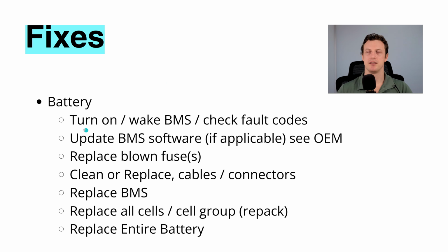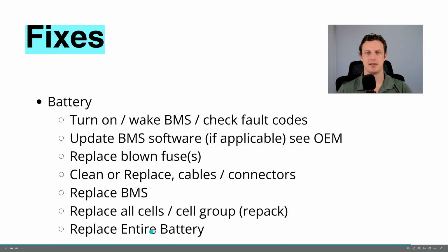For the battery, you can start by turning on or waking the BMS, or checking it for fault codes if it has that capability. You might also be able to update the BMS software if applicable - see the OEM of that BMS. Replace any blown fuses, clean or replace cables, wires and connectors, replace the BMS itself, replace all cells or a single cell group (which we call a repack), or replace the entire battery.